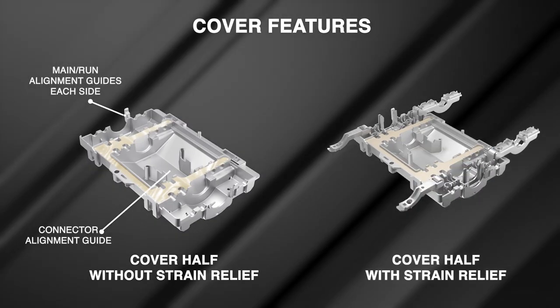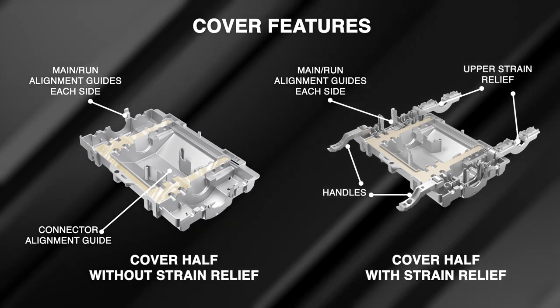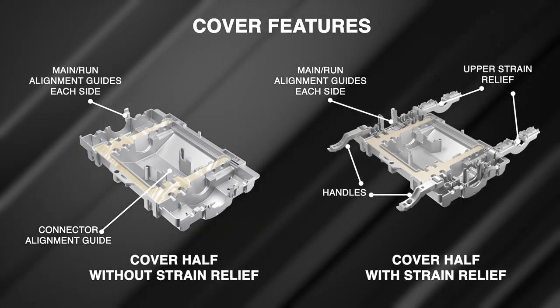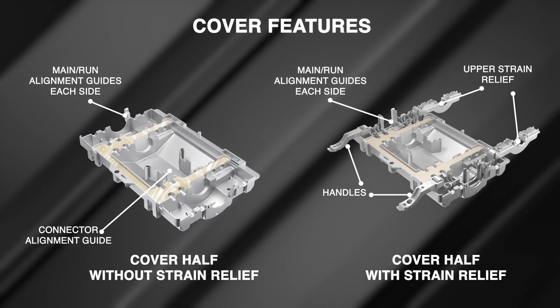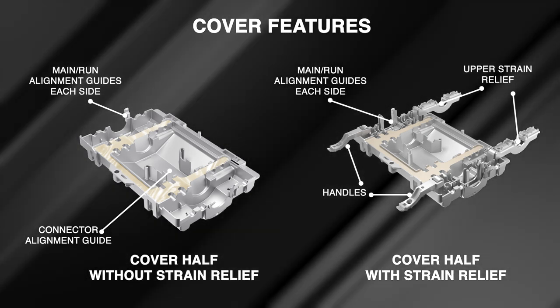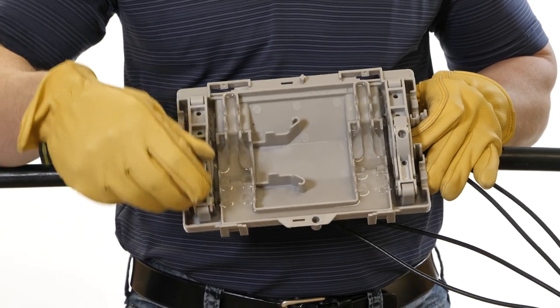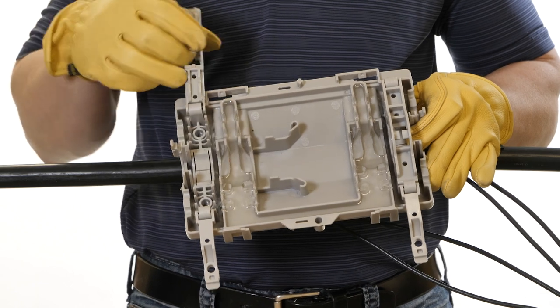Chapter seven: cover installation. When removing the plastic packaging from the covers, do not tear the packaging as some plastic could make contact with the gel. We want to avoid displacing or damaging the gel seal. If any plastic comes into contact with the gel, peel the plastic away slowly and the gel will set back into place. Start with the cover half that has the locking handles and strain relief devices.